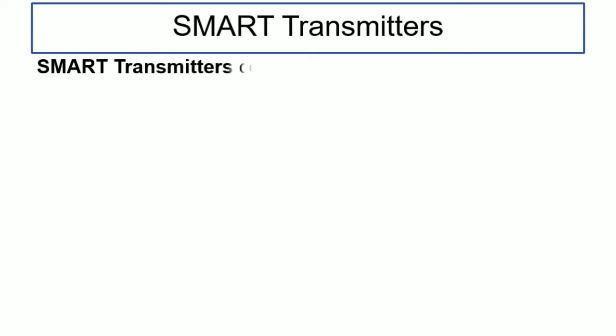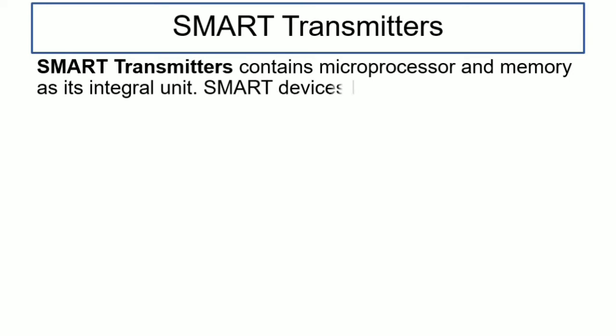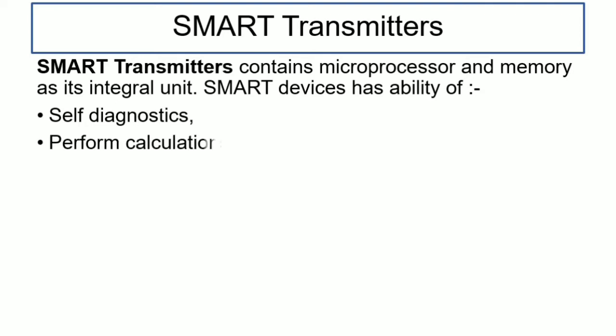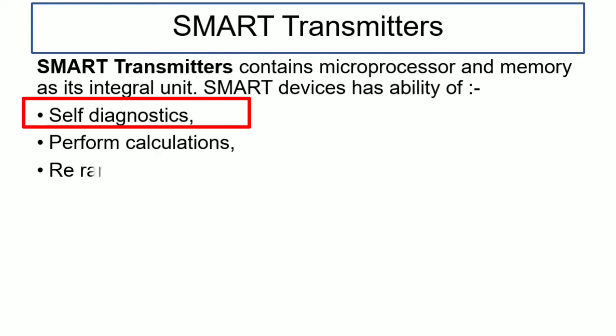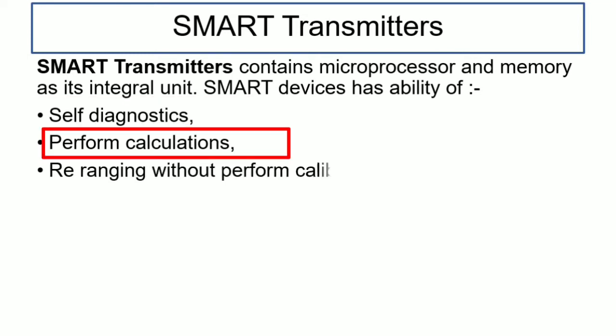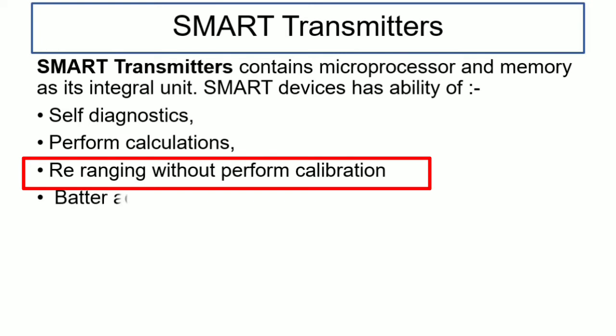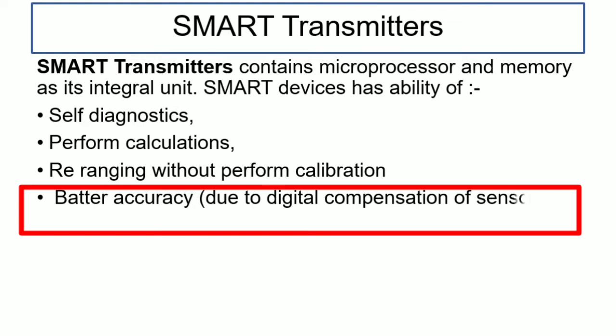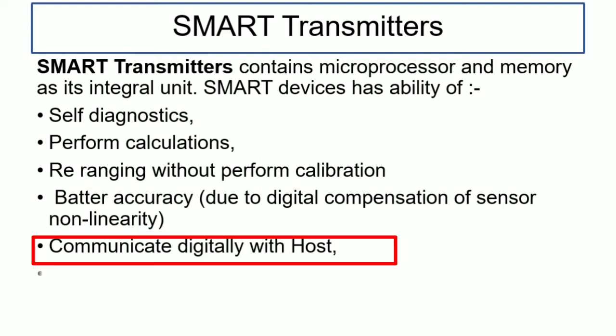Smart transmitters contain a microprocessor and memory as internal units. They have the ability of self-diagnostics, perform calculations, re-ranging without performing calibration, better accuracy due to digital compensation of sensor non-linearity, and can communicate digitally with the host.